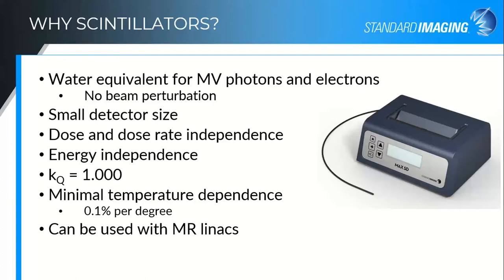That's the proof in the pudding that it's really not changing those interactions at the point of measurement compared with what would have happened in water. There is a small temperature dependence that has been seen over a large range of temperatures — about a tenth of a percent per degree. As long as you're at or near room temperature doing QA measurements, it really doesn't affect your data, so you don't have to correct for that.